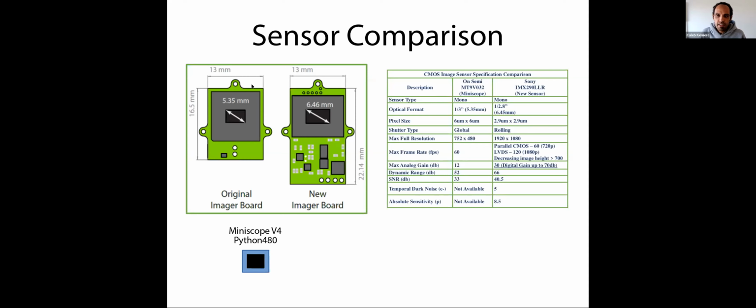But what's interesting about the original sensor is that the resolution is actually fairly low, and the maximum frame rate is also somewhat low. So we looked around and identified at that time what the best image sensor in this size range on the market was, and that was the family of sensors made by Sony that they call Starvis. They're backside illuminated CMOS, so they're at the cutting edge of technology in terms of making an image sensor that's maximally gathering photons. And in the game of fluorescence imaging, maximally gathering photons is the most important thing.